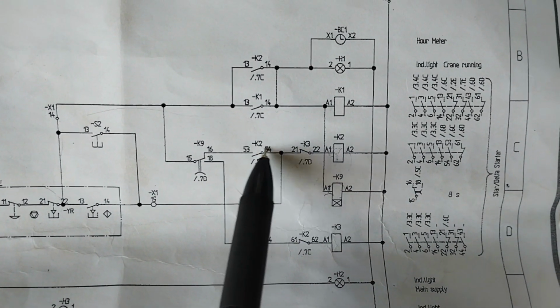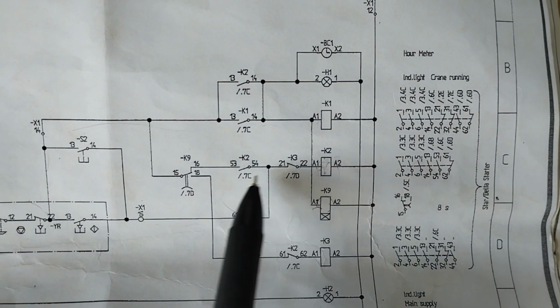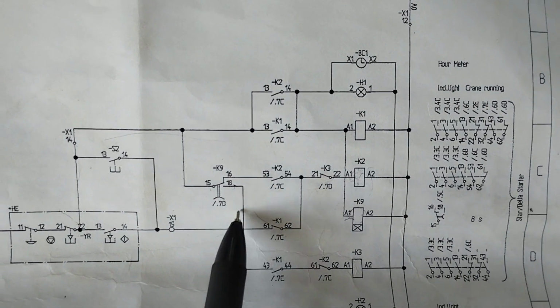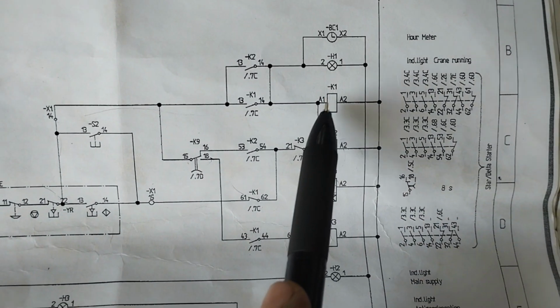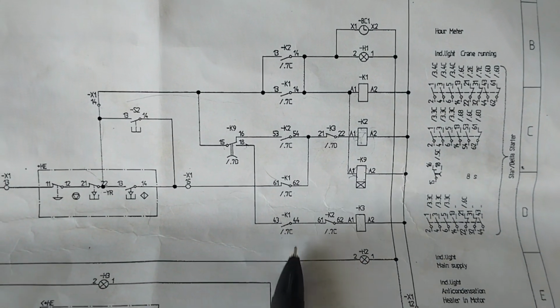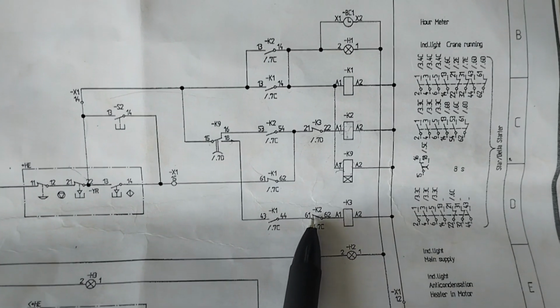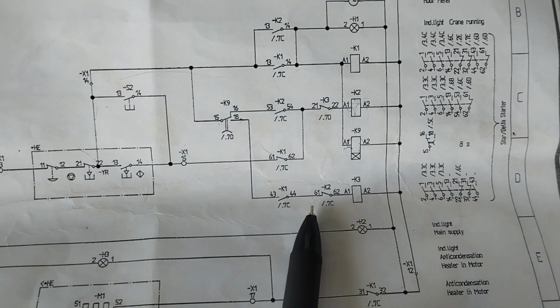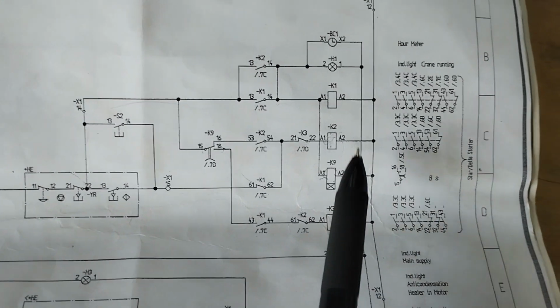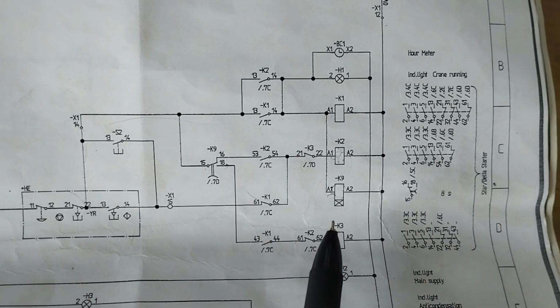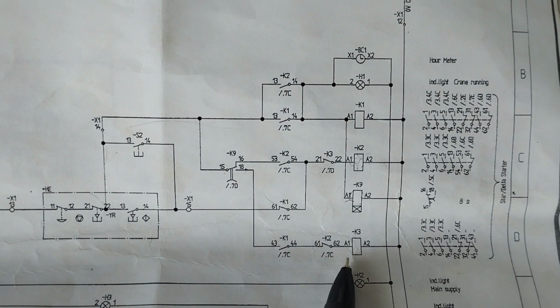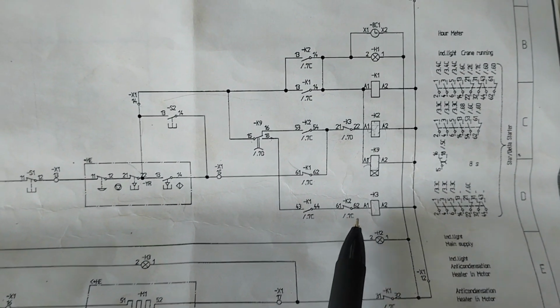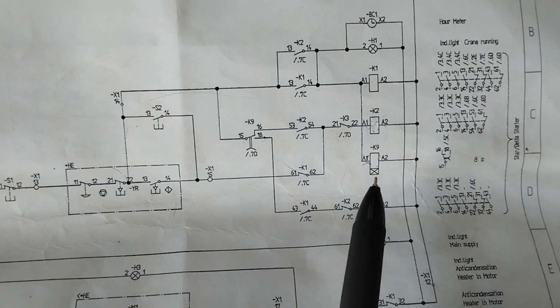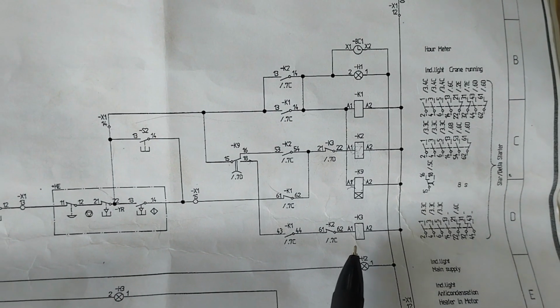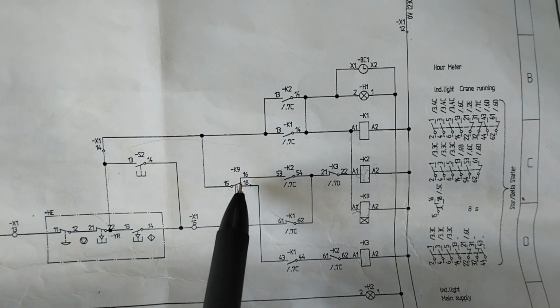So this is the holding contact of K2 which was energized before. When K2 is de-energized, this will also open, and 15, 18 will close. So power will come to here because K1 is already energized, and this is already closed. Now K2 is already de-energized, so this is normally closed, and K3 will energize. So K2 stops and K3 energizes, and the motor now runs on K1 and K3. Okay, so the motor runs at high speed, whereas before it ran at reduced speed. Okay, K2 and K1 in the star configuration, and after that the 5-second timer will de-energize K2 and energize K3, and the motor runs at high speed.